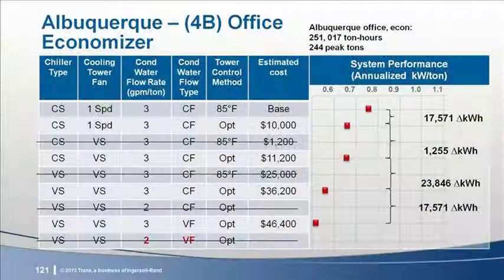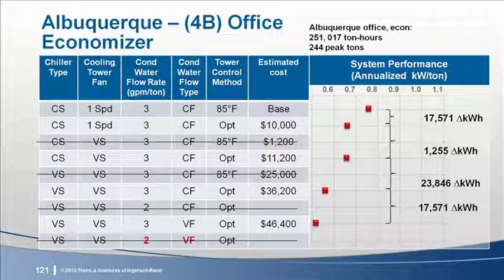Here I've changed to the Albuquerque office building with an airside economizer. Those paybacks that could be as short as a few months are now several years. Even though we improved by 29% over a respectable base of 0.785 annualized kW per ton, going all variable speed won't save as much money due to the shortened cooling season and lower peak loads.